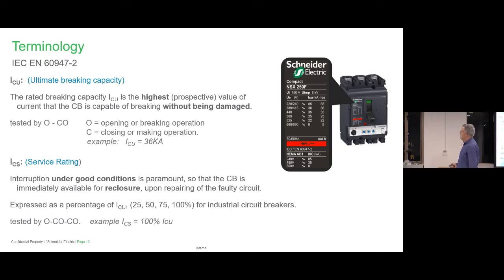But the reality is, some of them can't. Some of them are derated. You need to know this. We don't derate ours, but this is what they are. Some of them can be 50% of that value, can be 75%, even less than 50%. So just be aware of that. It's important because of what you've determined your prospective fault is when you do your design. You need to know this.